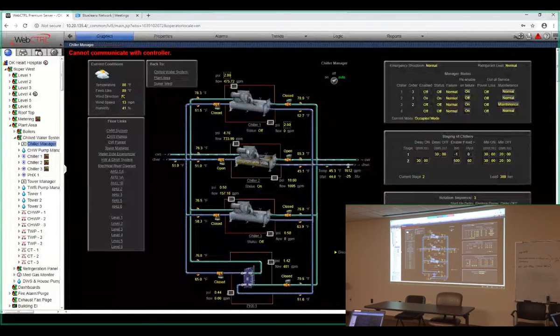Overview of the graphic, still got the floor plan links, major system links on the left side, the weather data. Got some shortcuts back to the chill water system, the plant area, or the main super west. Each chiller has a differential pressure across each barrel, so we're measuring differential pressure on the chill water and on the condenser water. That is what we're using to calculate your tonnage, your load: that pressure, the flow, and the temperatures. Each chiller has its own isolation valves and condenser water, chill water supply, and return temps on both sides of the chiller.